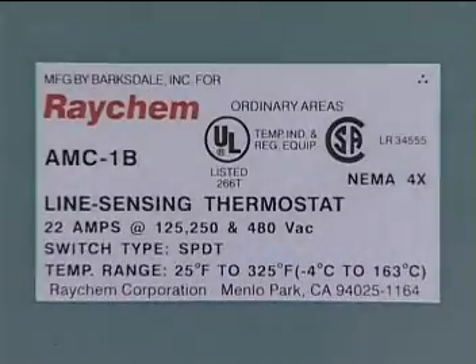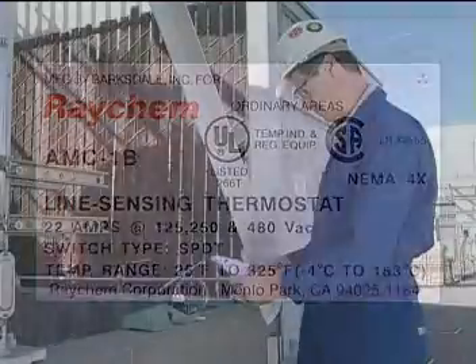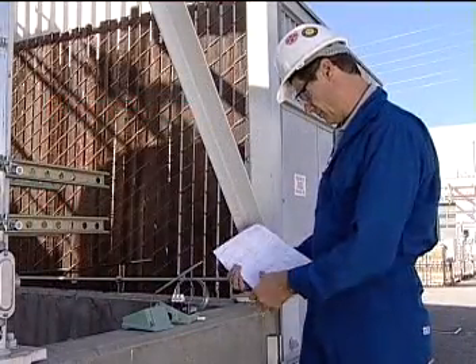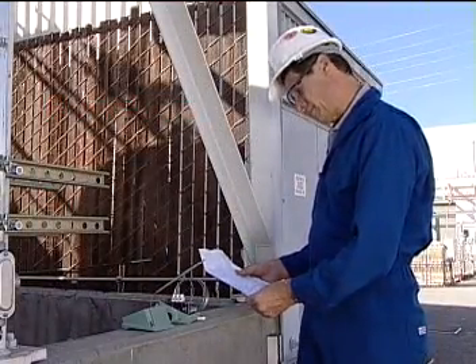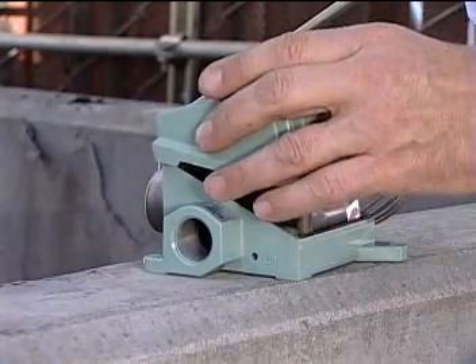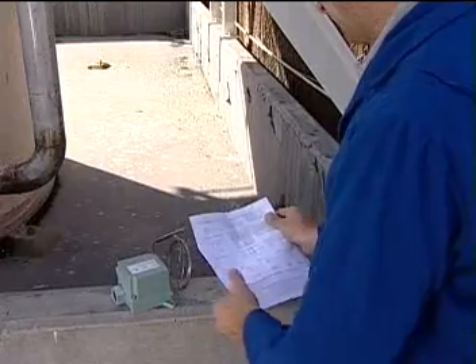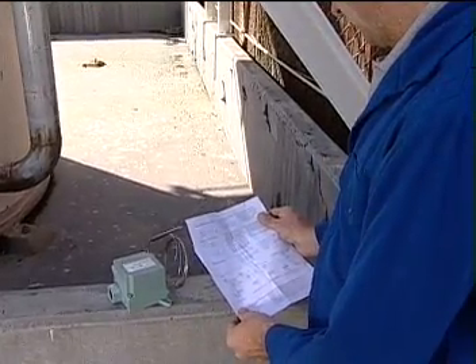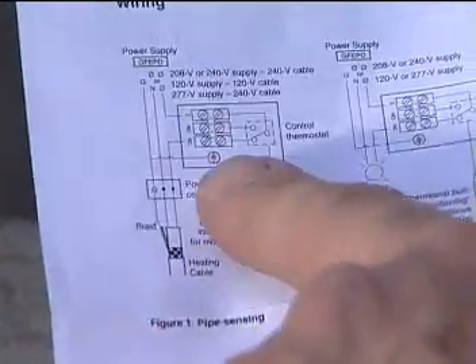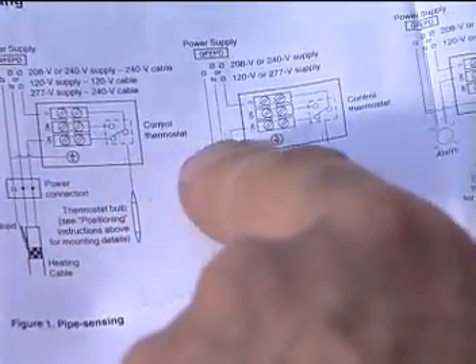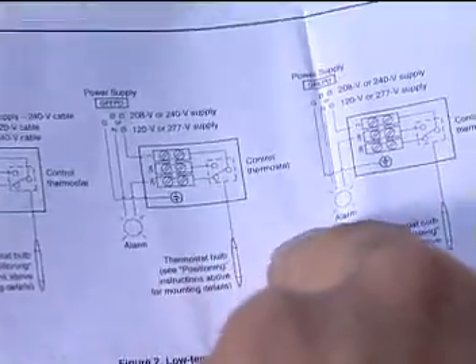Before mounting the thermostat, check to make sure that both the voltage and the heater load are compatible with the thermostat, and that its NEMA rating is appropriate for the area of use. Remember, when you're working with any type of thermostat, keep the cover closed to avoid exposure to the elements. Also, refer to the thermostat's wiring diagram to check if it's intended to control the heating circuits directly or to control the coil on a contactor.